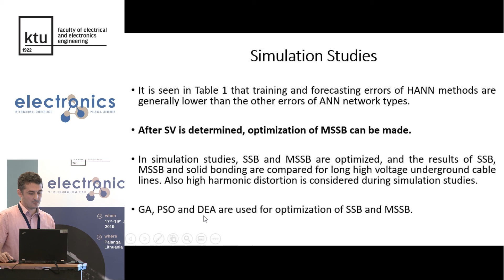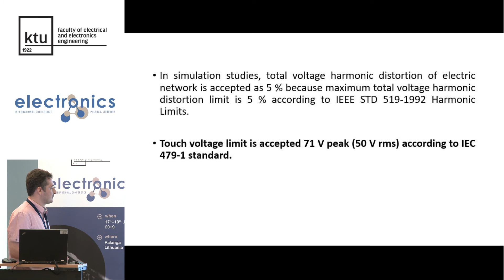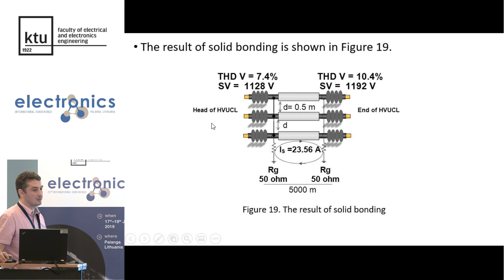In simulation studies, SSB and MSSB are optimized, and results of SSB, MSSB, and solid bonding are compared for long high voltage underground cable lines. Also, high harmonic distortion is considered during simulation studies. Genetic algorithm, particle swarm optimization, and differential evolution algorithm are used for optimization of SSB and MSSB. In simulation studies, total harmonic voltage distortion of electrical network is accepted 5%, and touch voltage limit is accepted 71 voltage peak. The result of solid bonding is shown in figure 19. In this bonding, SV is bigger than touch voltage, and harmonic distortion is bigger than limits.